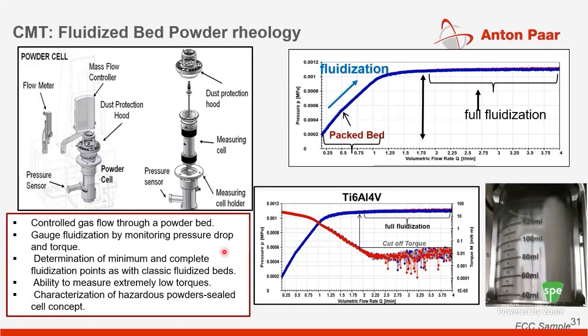where you can understand at what point the material fluidizes. And the other unique thing about the setup is that since this is coupled to an air bearing rheometer, and you also have a spindle connected to the top head of the rheometer, you can study the evolution of torque as a function of flow rate, and understand at what point the material completely fluidizes. Coupling it to an air bearing rheometer really helps to characterize very low torques. If you look at most powder devices which people use in the industry, they are mostly mechanical bearing devices. So having a powder rheometer on an air bearing device really opens up new experimentation when it comes to characterizing materials at really low torques, which is very important for fluidization experiments.